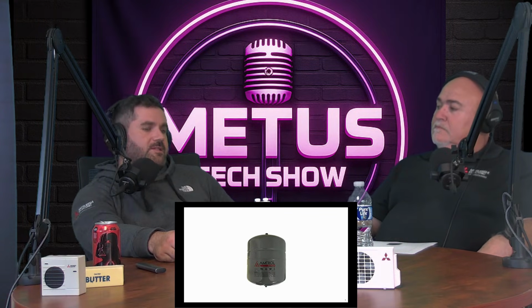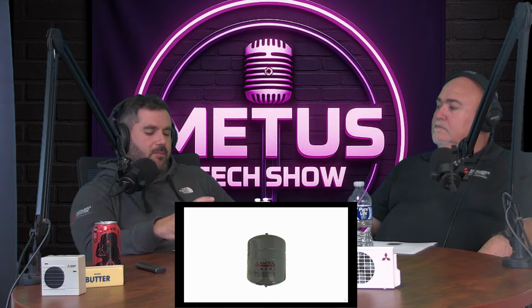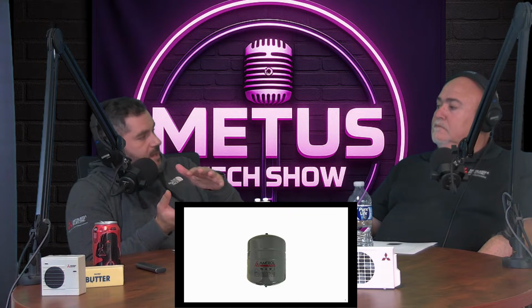So speaking of pressure, let's go to expansion tanks. So again, another thing we've probably covered in past podcasts. The way that I like to describe an expansion tank is you see this metal barrel, and the bottom half of it, inside of it, is this rubber bladder. And I think of it like the inside of a basketball, right? And you inflate that basketball, the rubber bladder pushes up against the leather. Same thing is happening in here. You have this rubber bladder that's on the bottom half of that expansion tank. It's set to a certain pressure, and it fills up. Usually it's about half of that expansion tank.